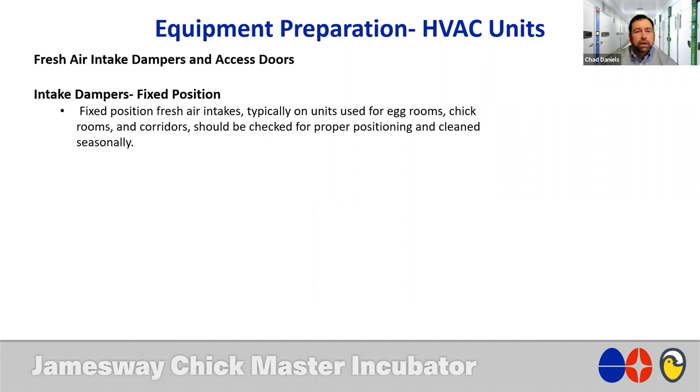I'll visit hatcheries a lot of times, especially in the summer when high humidity conditions in egg rooms exist, and you'll go to the roof and look at the outside air intake damper on those units, and even though they're fixed, someone has moved them to a closed position, and they've done that probably to try to help maintain the environment a little bit better in the room. So it's a good idea seasonally to always check those.